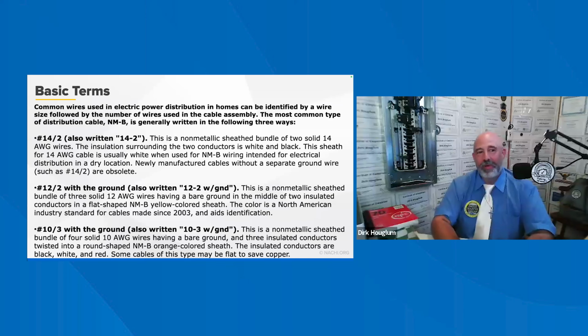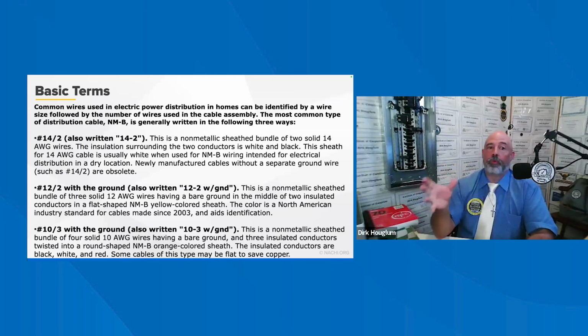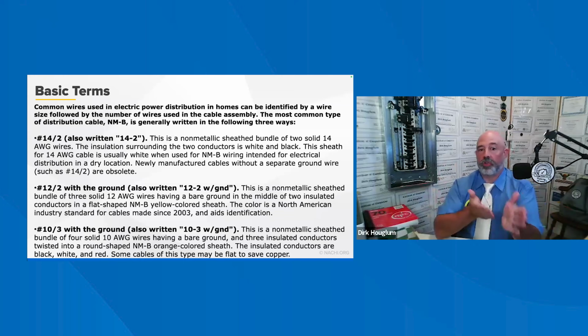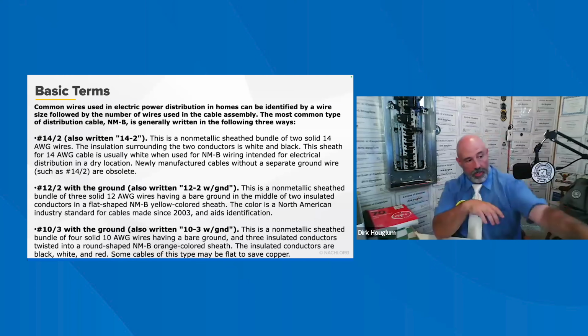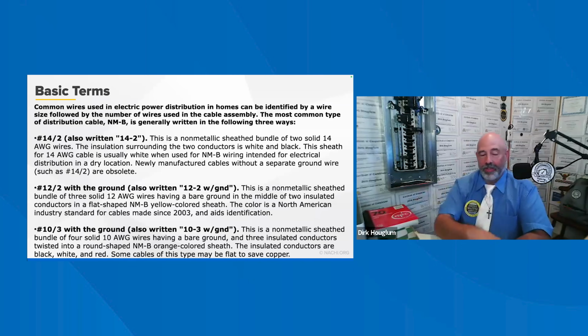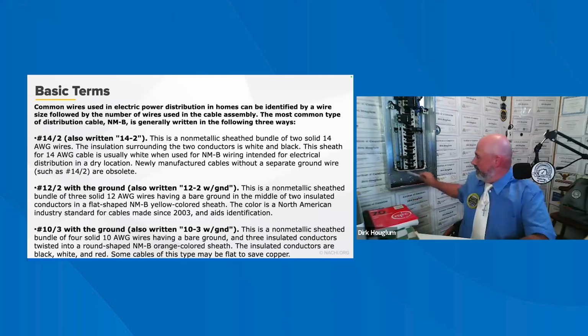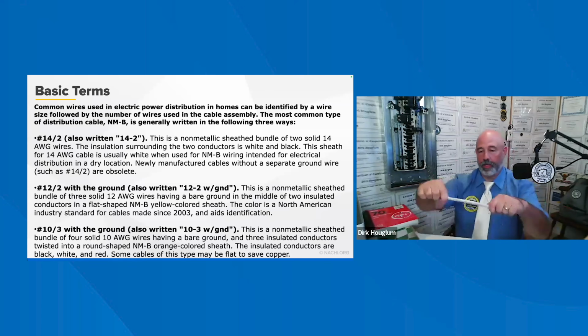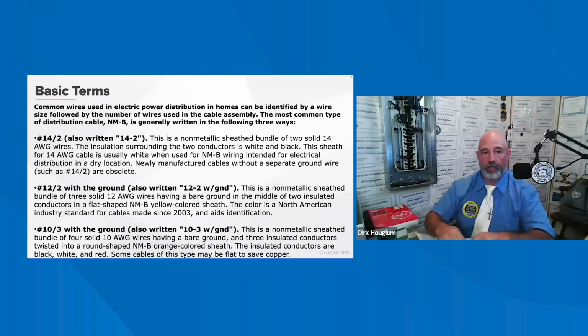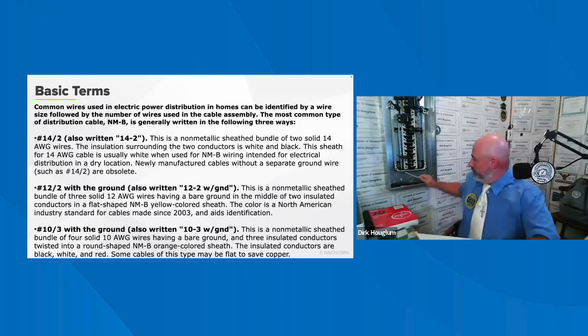So there are common wires used in electrical distribution in homes, and they can be identified by a wire size followed by the number of wires in the cable assembly. So for instance, a 14-2 would be two solid 14 gauge wires. Now, if there was a grounding conductor on there, it would be a 14-2 with ground, okay? Or if it was 12 with ground. And that's how they actually put it, exactly like that. And you can read it right on the sheathing of it. So like this 14 gauge wire, I can't read it without my glasses, but it does say it on there. That's 14-2 with ground. Okay.